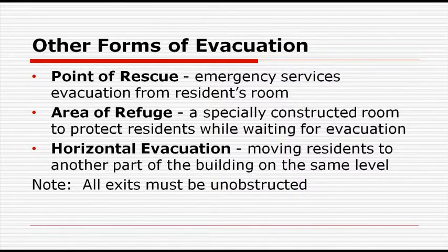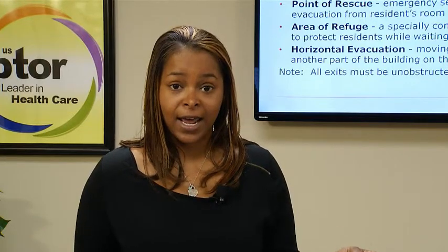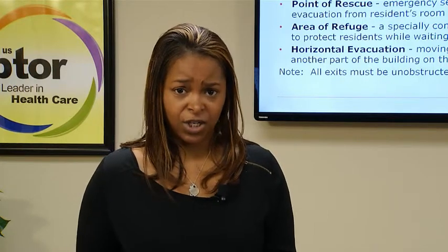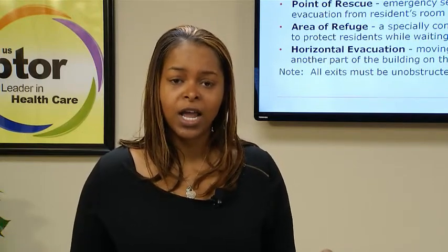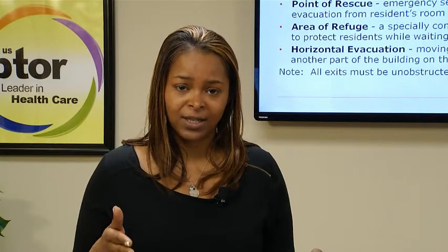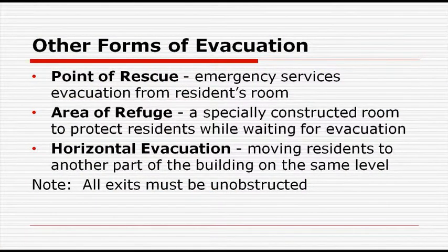Horizontal evacuation. Depending on the facility structure and size, some facilities may use horizontal evacuation as the first step in resident evacuation. The ability to use horizontal evacuation depends on the construction of the building, including the presence of smoke and fire barriers. An example of horizontal evacuation would basically be, let's say I work here in the ICU and there's been a fire. And instead of exiting the building with our patients, what we would do is we would go right next door to, say, the OR. And in between the ICU and the OR is a smoke door, separation door with at least 60-minute rating, and a smoke wall. Okay?